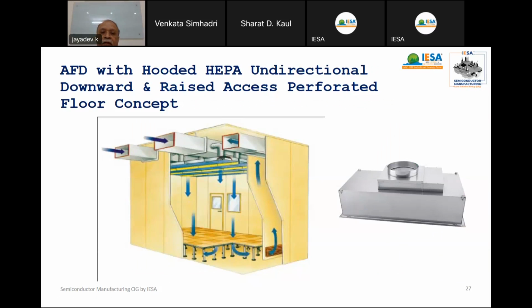So this is a picture of another method, an airflow diagram using hooded HEPA. This is for mixed flow, not unidirectional. Sometimes we can use unidirectional also, using downward flow with raised access floor. But here, instead of FFUs, you will have HEPA filters.